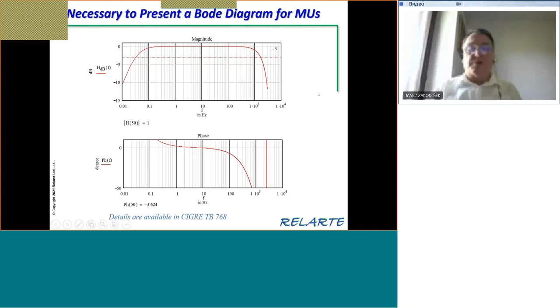And in this technical brochure, which I mentioned before, you will also see that we suggest that always the producers of merging units, and also those producing non-conventional instrument transformers, should provide their Bode diagram for frequencies, let's say, practically from 0 Hertz up to at least 5-6 kilohertz, if not even more. Because only in this way will those producing protection or measuring elements be able to ensure correct functionality of their own equipment. Again, you can go into this technical brochure to see all this.